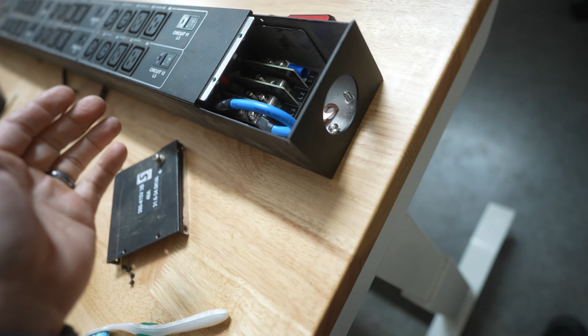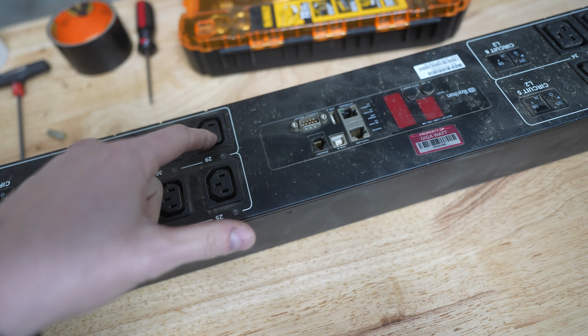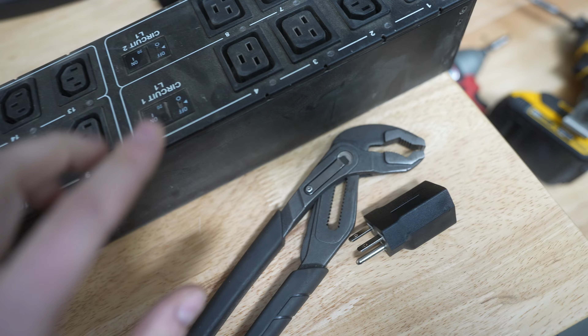Because you just have a bunch of stuff plugged in. You have a monitor, another monitor, another monitor, whatever. This is made for servers, so you might have something running here at 200 watts and something here at 100 watts, and 300, 200, 400, 200, 200, 300, 400, and so on. So you need a lot of plugs, but you don't really use all 20 amps. In our situation, we're actually using 2,200 watts per plug. So we plug this guy in, and it's already at 22, 22, 22, 22, 22, and so on. So you've got to spread it out to hit that 35.